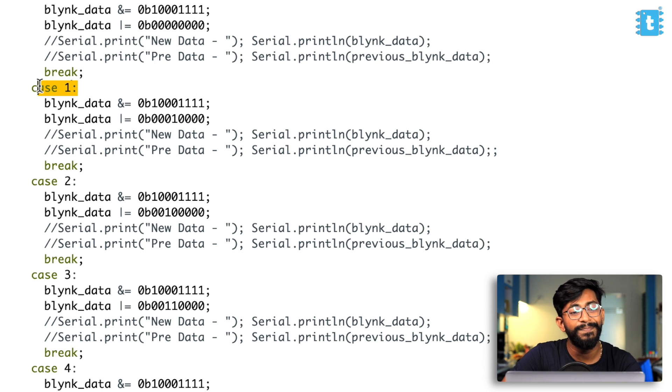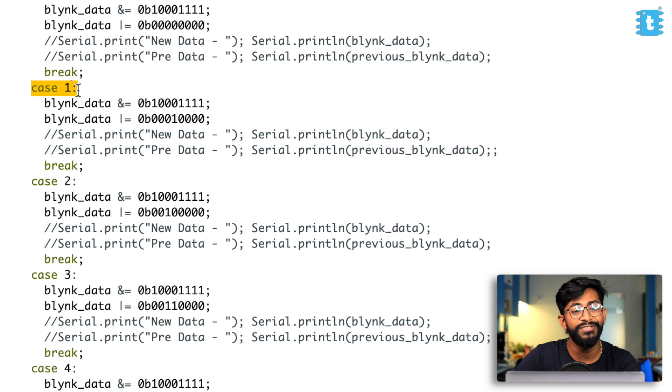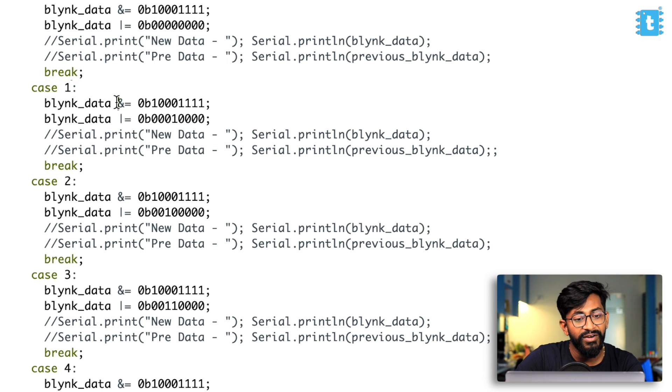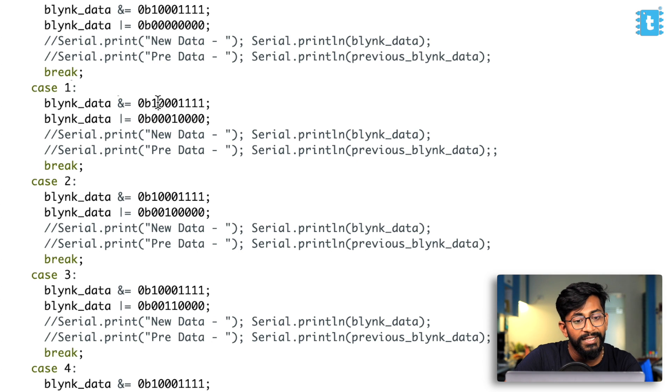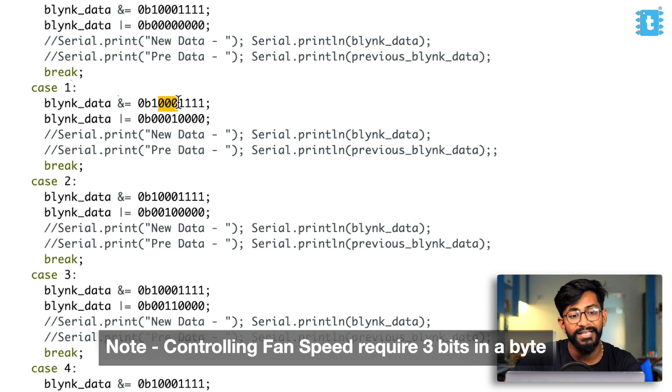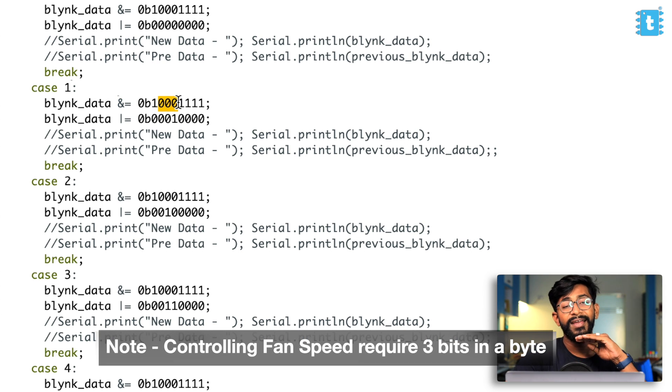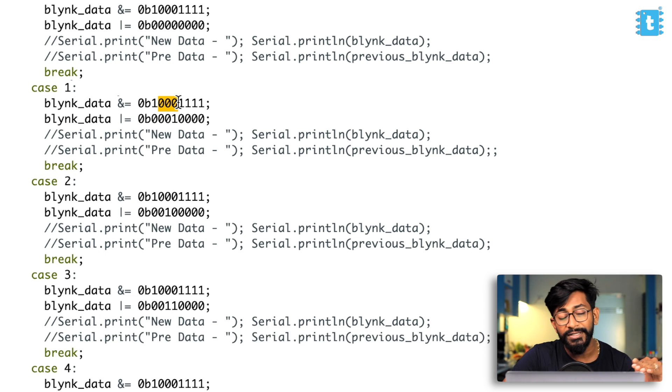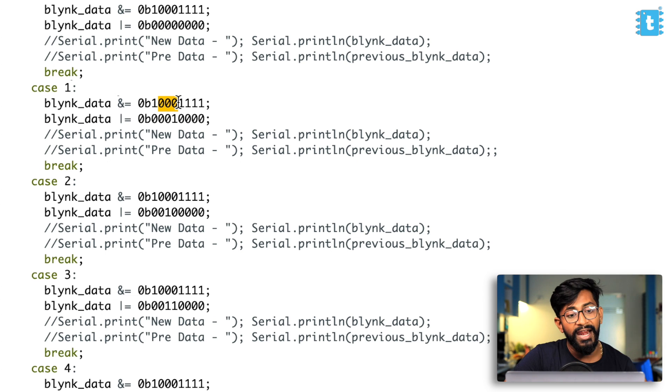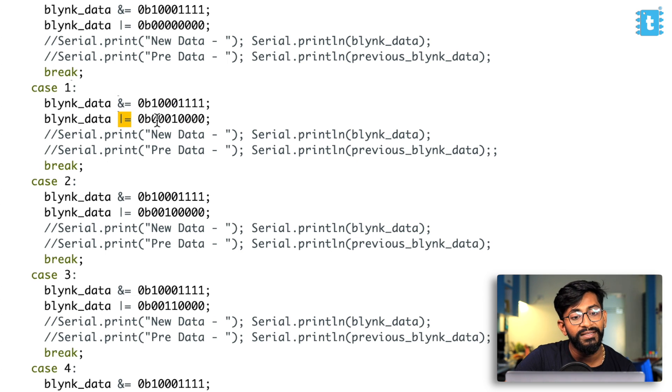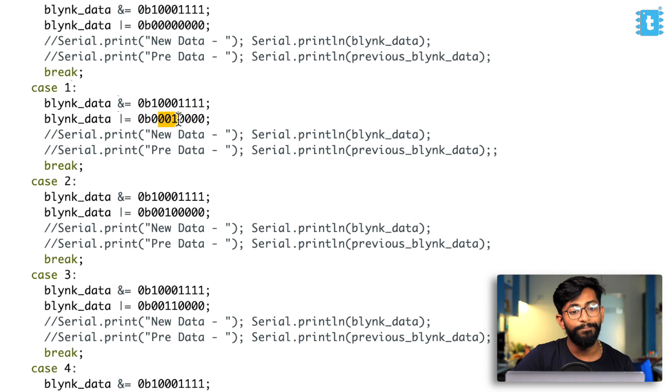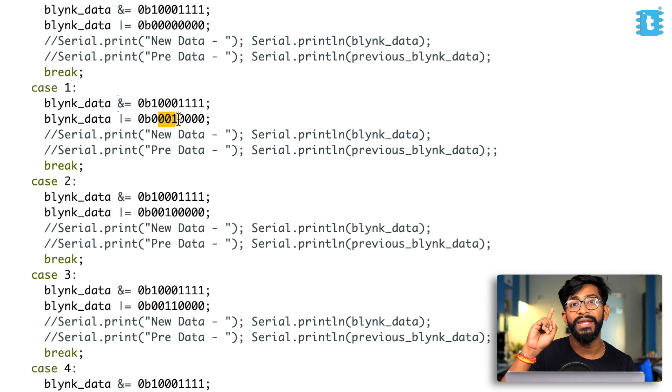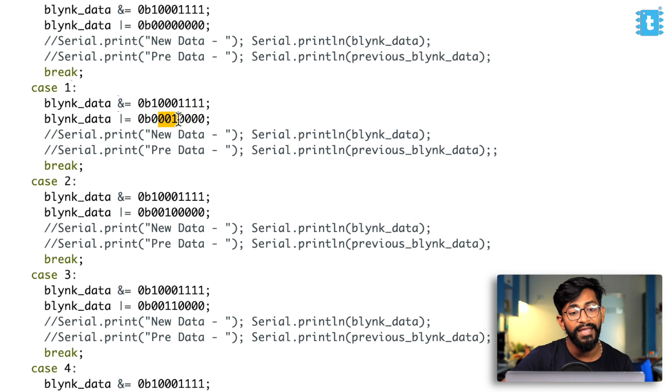So let's assume that we have received the speed one from the mobile application. So this condition will be satisfied. So first of all, we are ANDing the logic with all the three bits as zero. So means we are clearing all the three bits of the fan speed control. And after that, we are ORing that with zero zero one. Zero zero one represent the speed one of the fan.